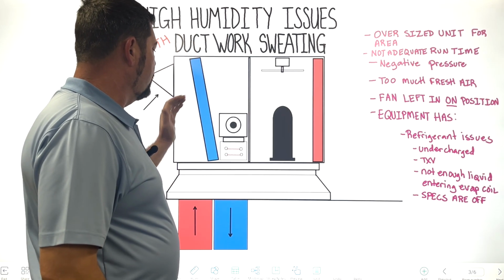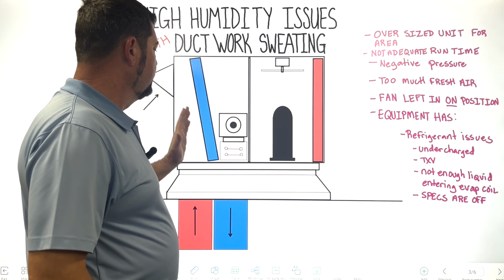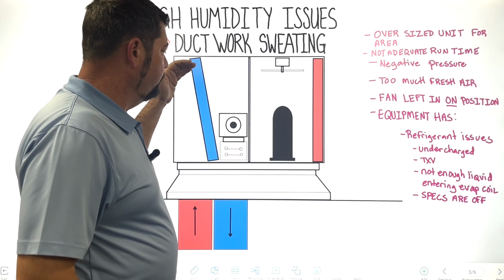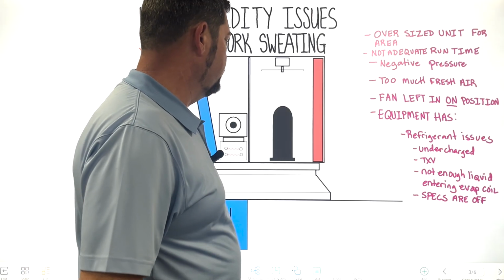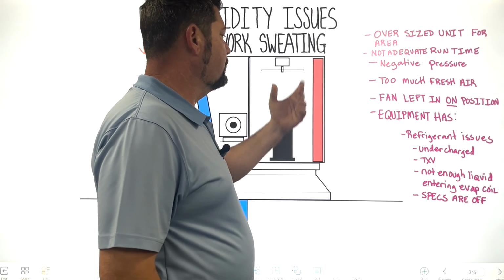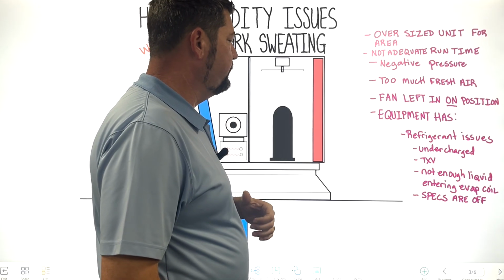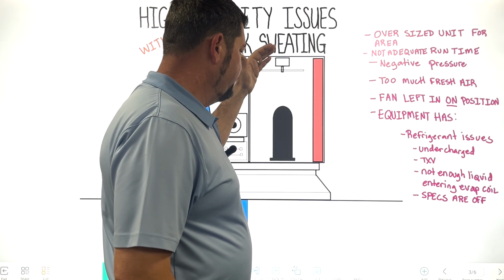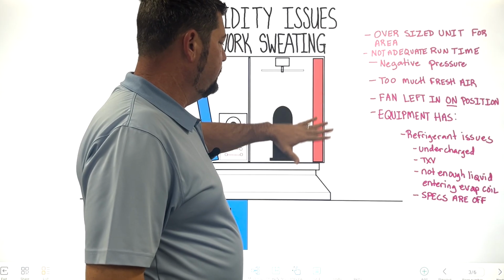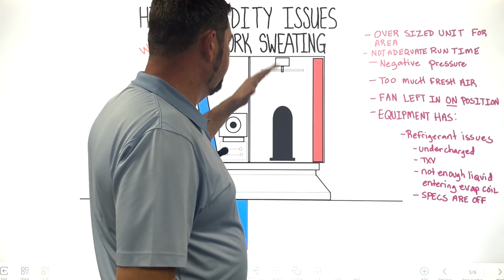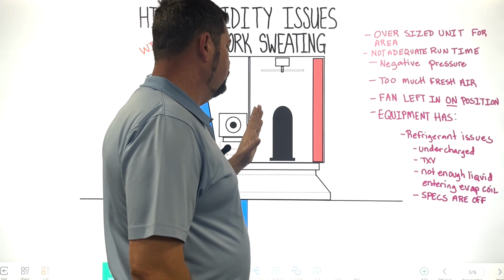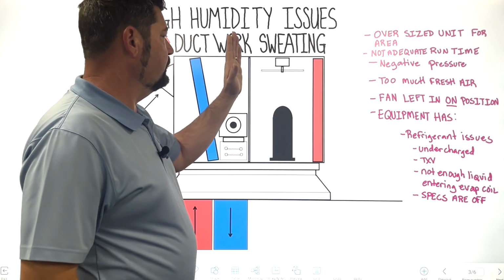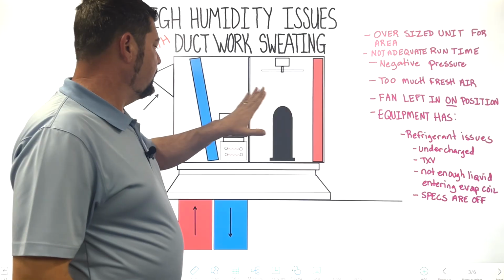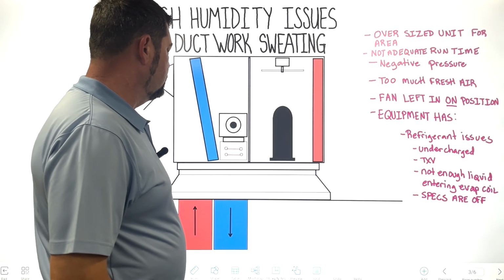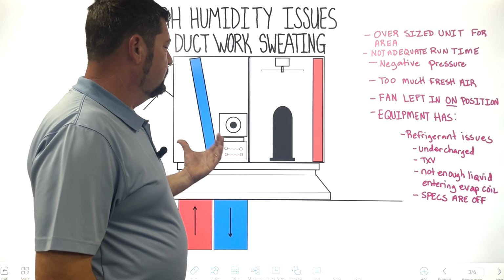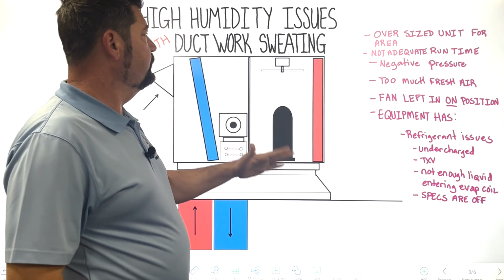Then the rate of air going across this evaporator coil is now going to allow the system to remove less moisture out of it. Condenser fan motors may not be turning at the proper RPMs because they were swapped out with something that's out of specs that now is not balancing the head pressure properly, and you can't get the right charge because of that. Anything that's going to relate to the refrigerant not being charged right because of either the demand of airflow on the condenser section or the demand of airflow here, anything like that is going to cause a higher humidity.